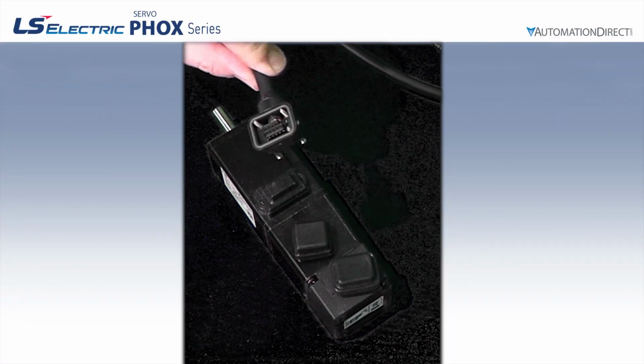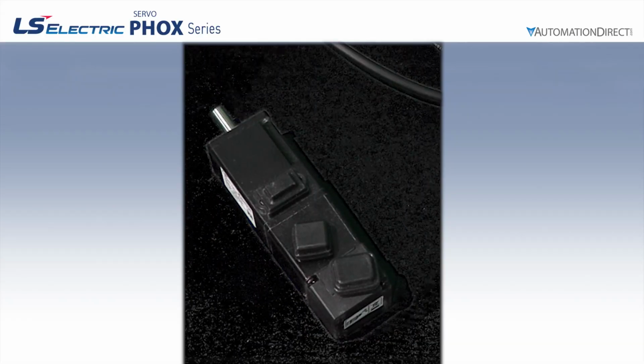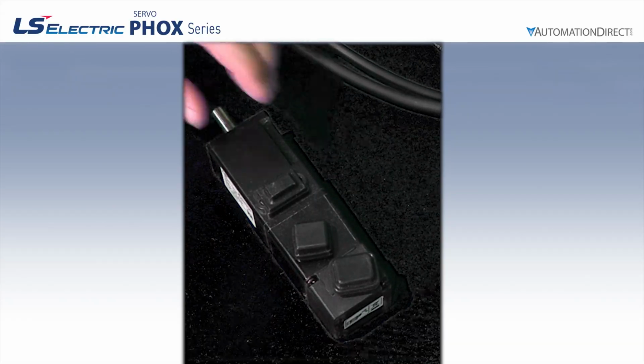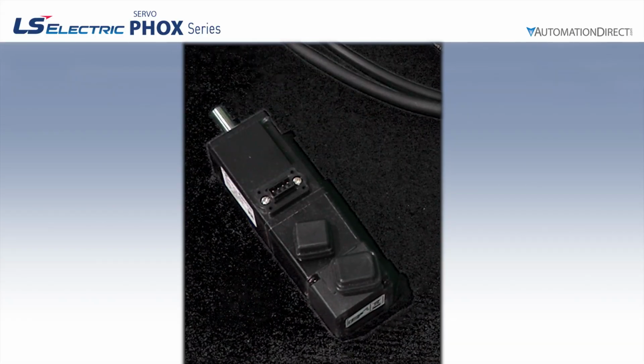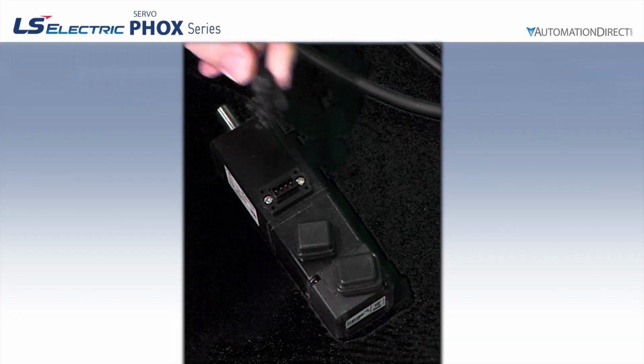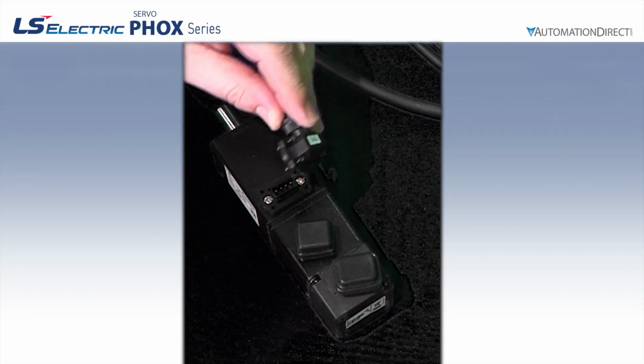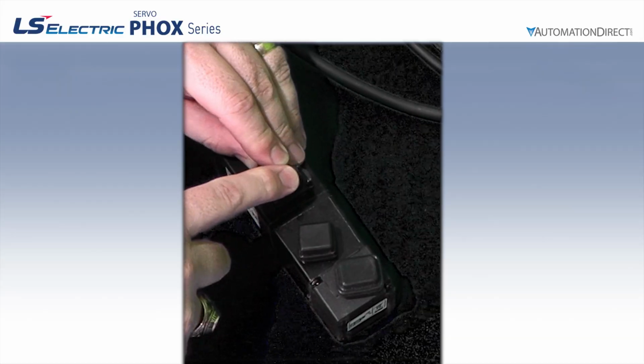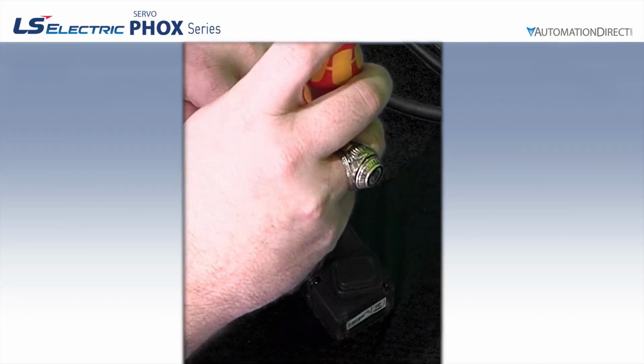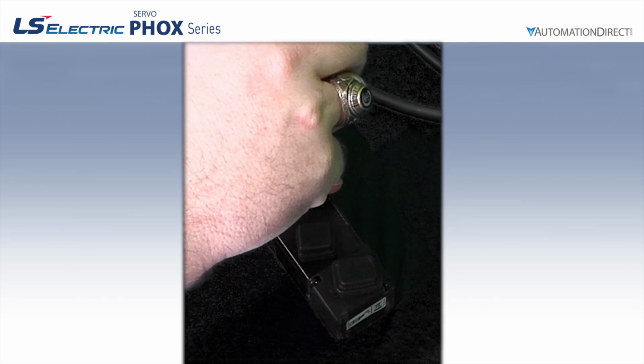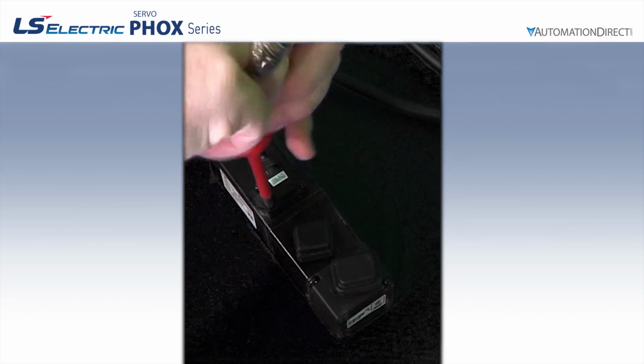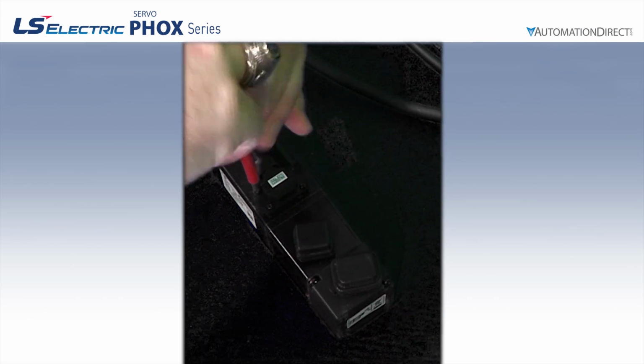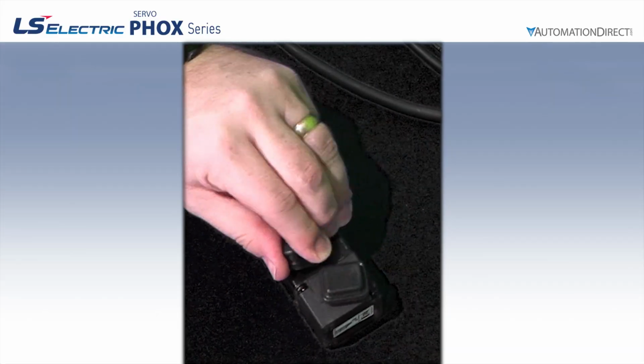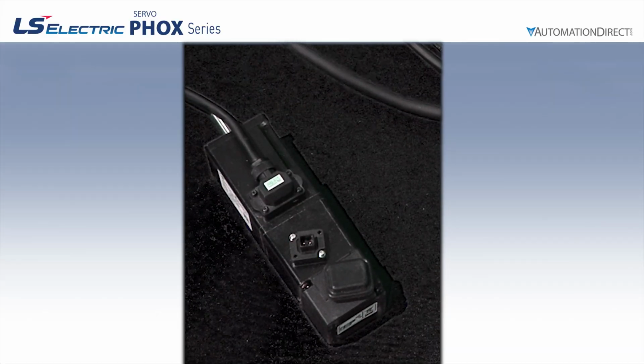This connector is keyed so it can only be attached in the correct orientation. Remove the rubber boot and place the power cable onto the connector head. Align the small screws in the cable head with the holes on the motor connector, and gently press the head down until it's fully seated. Then tighten the screws. Do not over-tighten, as the screw heads are small and easily stripped. Next, if you have a braked motor like we do here, connect the motor brake cable.